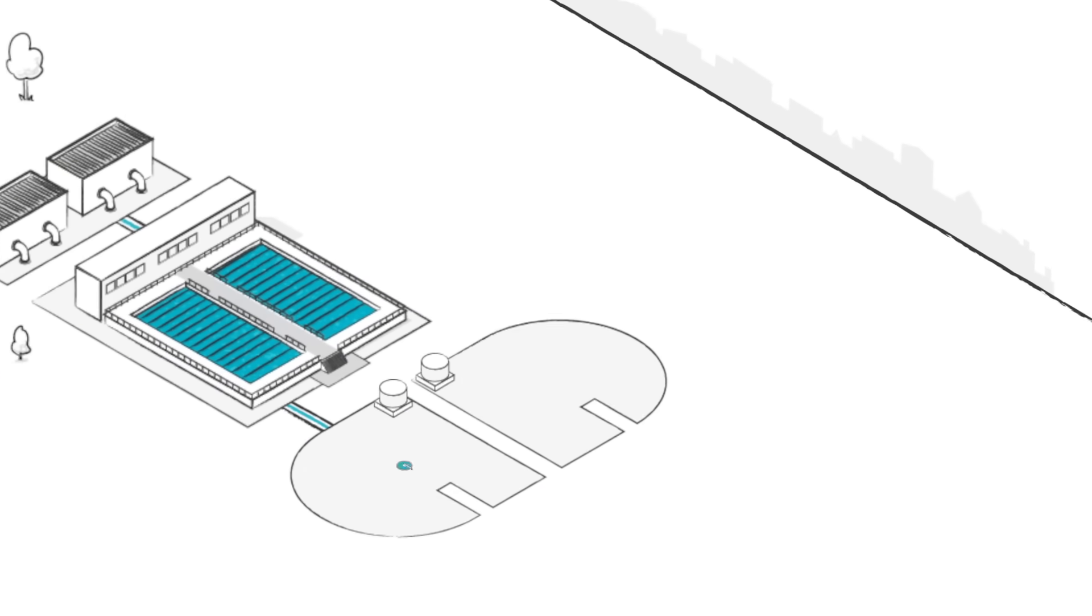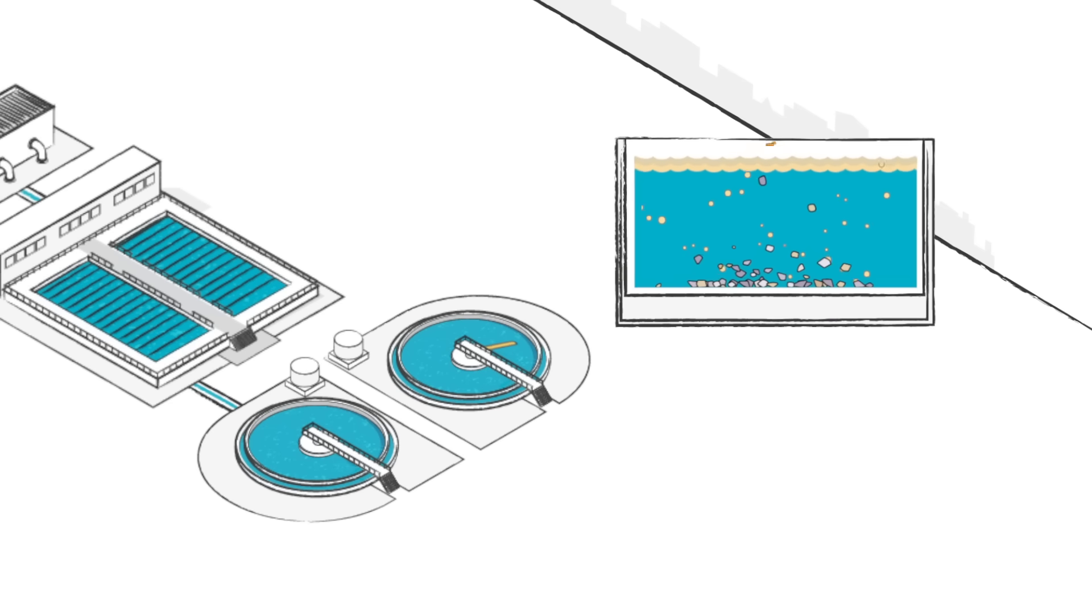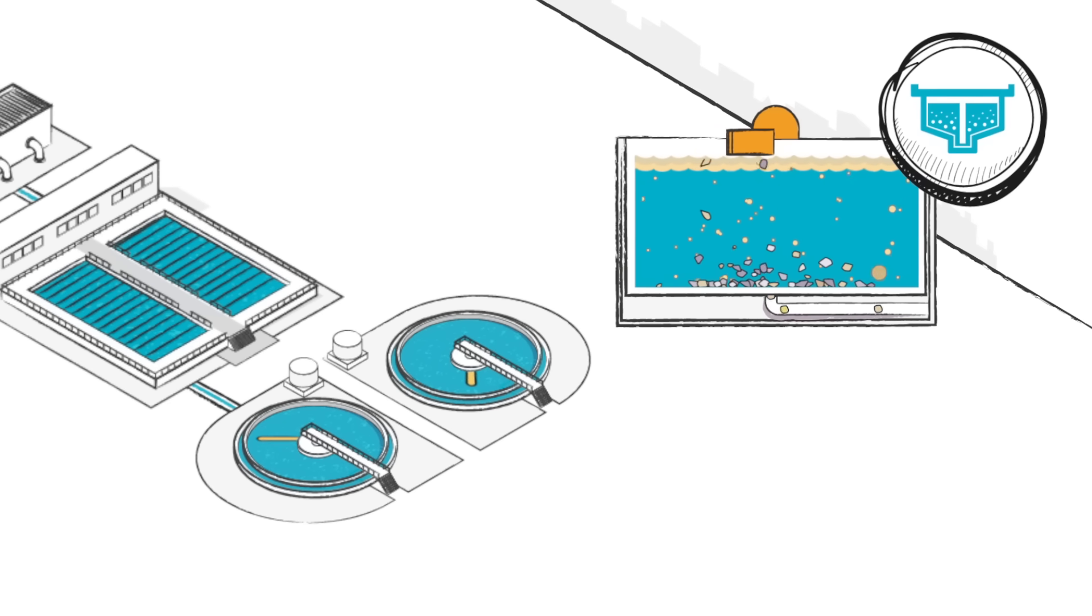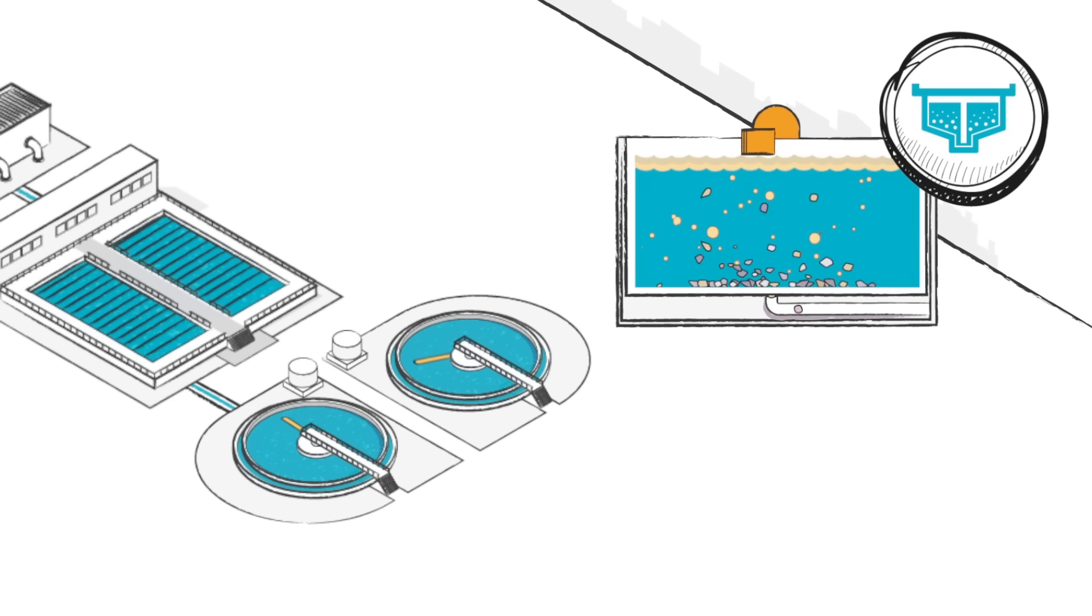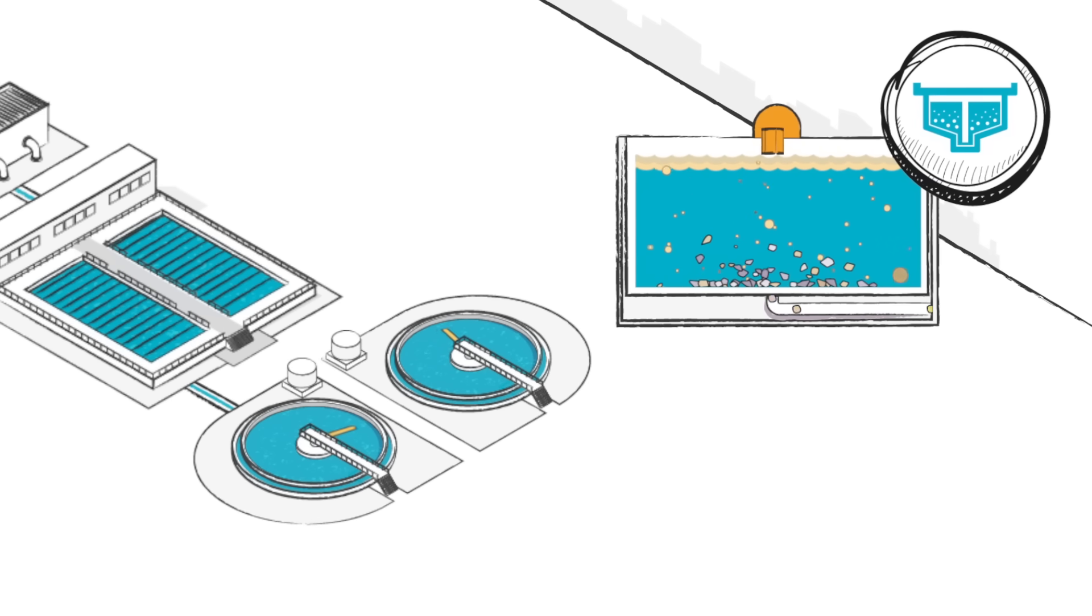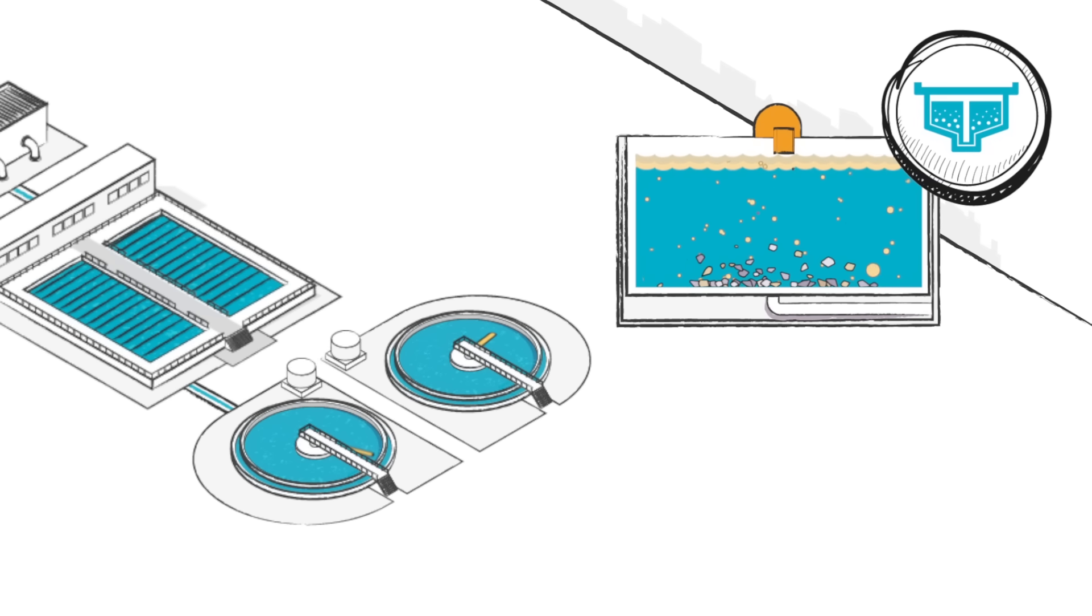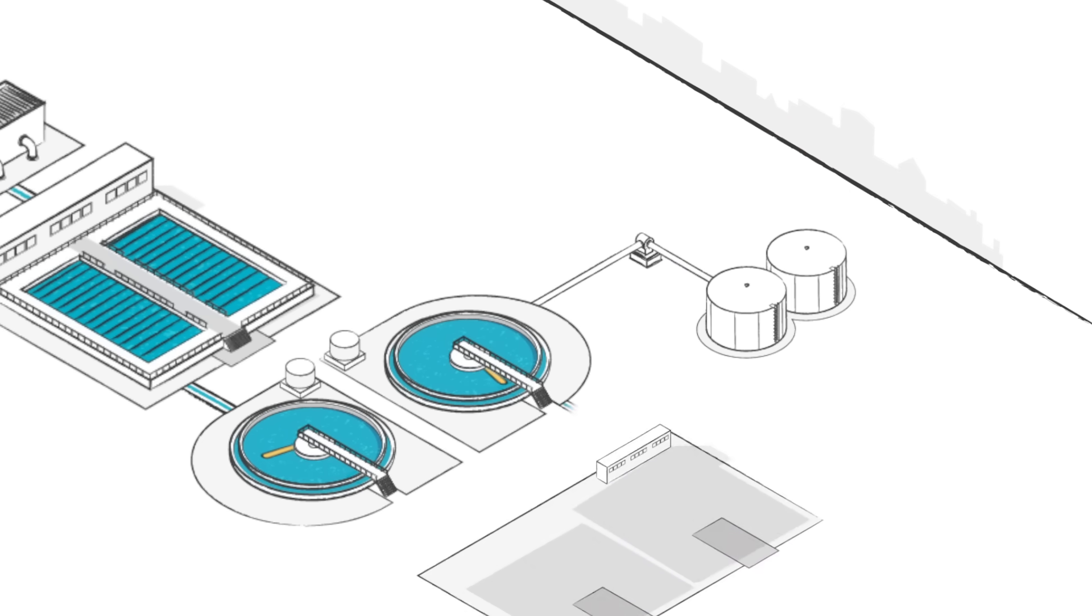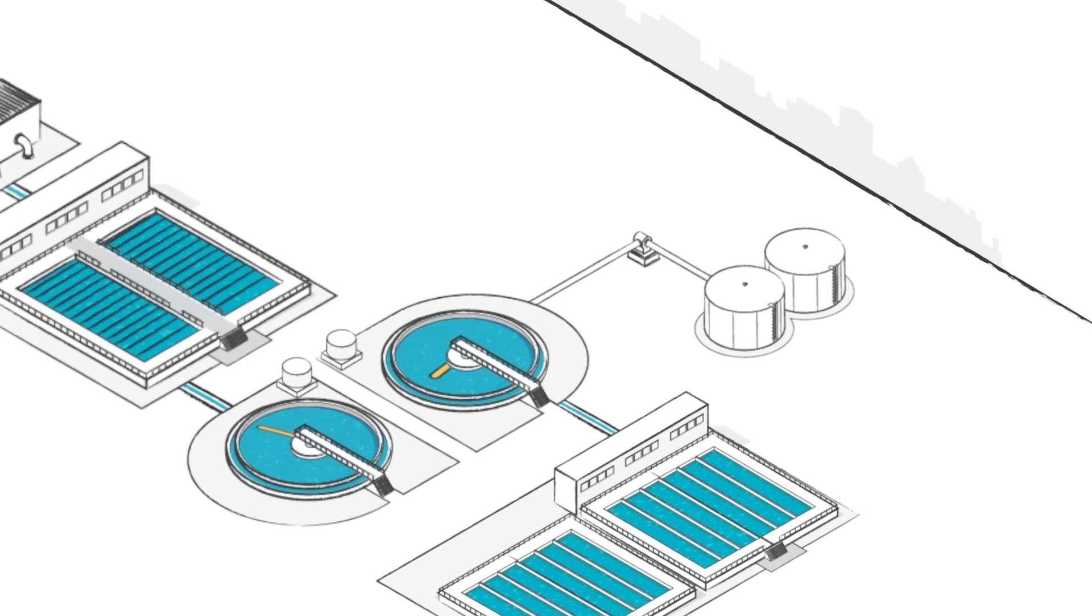The water is then sent to large clarifiers to settle. An arm that takes an hour to rotate once skims off fats, oils, and grease that float to the top. Any solids that sink to the bottom are scraped off and pumped 12 miles to anaerobic digester tanks at South Shore, where the gas is captured and used to help power the plants.